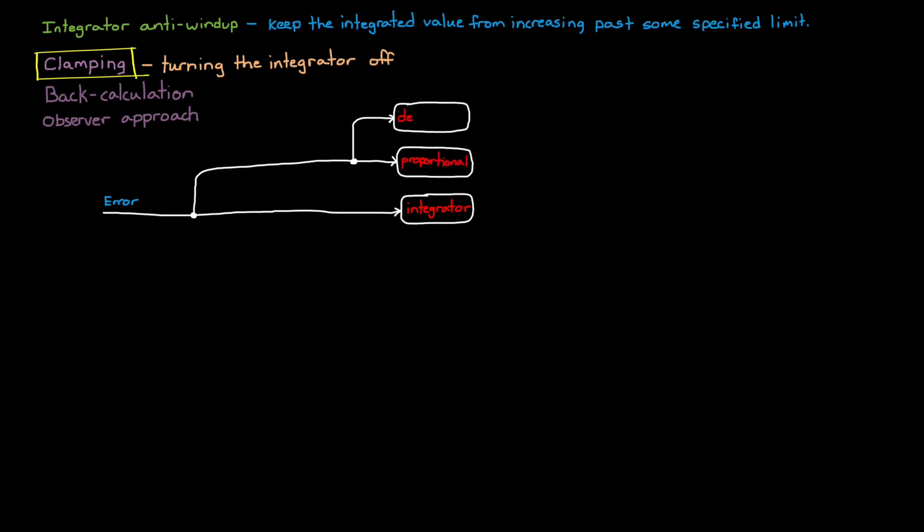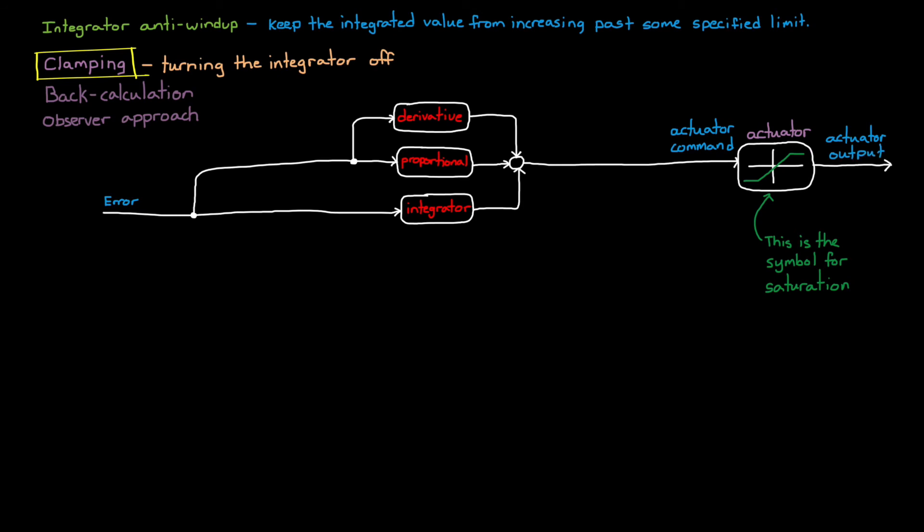We'll start with our familiar PID control law that acts on the loop error and generates an actuator command. But as we just learned, sometimes an actuator can't follow the given command, and it saturates. So even if a large actuator command comes in, the output will be capped at some value. So the first thing we want to do with our PID controller is make sure that it doesn't output a value outside of what the actuator can handle. We can do that by simply limiting the output of the controller with its own saturation check.